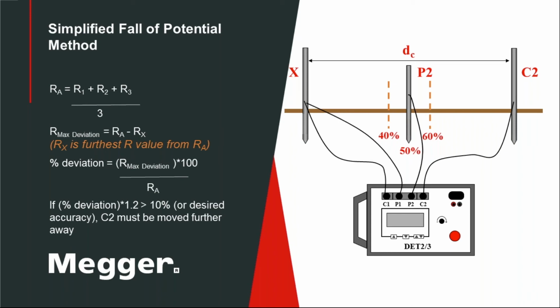So you've got 3 numbers instead of 10 or 20. On the left there's a simple mathematical equation you plug those numbers into, and that calculates your percentage accuracy. The average of those 3 numbers will be your correct number within a certain percentage accuracy, just like you get on any DMM. So if you have a good 1% or 2% accuracy, you're fine. If you've got like a 10% accuracy, you're probably not going to be too happy with that, so you'd try it again. And that's your simplified fall of potential.